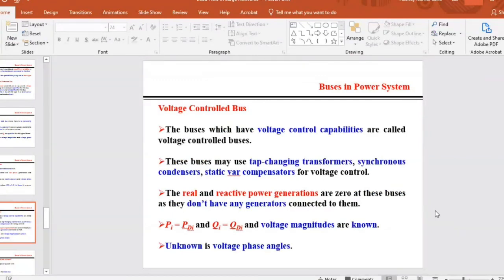The last type is called voltage controlled buses, meaning we need to control the voltage because loads are consuming power, currents are flowing, and because of current flow there will be voltage drops. We need to compensate for those drops, otherwise we reach a condition of voltage instability. We must remember that if there is no voltage, current cannot flow. If current is not flowing, there will be no power, meaning the system is not there—it's unstable, reaching a condition of instability.